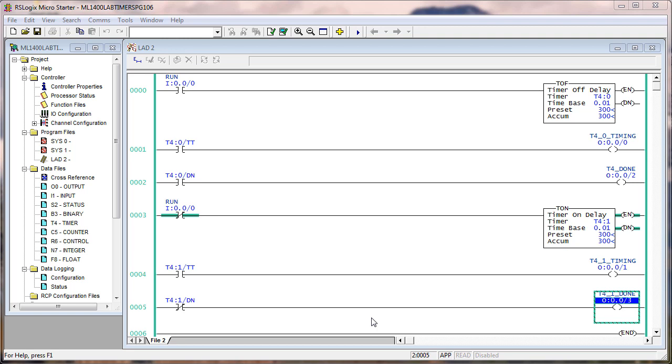The answer that you came up with is correct if you consider the question properly. Right now, if you look at the timer timing bit and done bit for T4-0, they are both off. If you look at the timer timing and done bit for the TON, one is on and the other is off. Meaning that with the run input off up above, run zero, with that input off, that bit memory off, then the TOF is not enabled. But we inverted that state to run the TON.